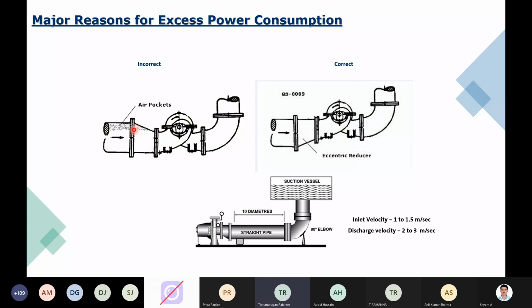So in this case, you can find this is a suction side adapter, which is used to mate your pipe and your pump flange. This particular design will facilitate an air pocket always. So that keeps the pump from performing to its potential. And this can be corrected with this kind of eccentric reducer, where the water is always filled in this particular zone, and whenever the pump starts or stops, there will not be a point of air entrapment in your suction or in the pump itself.